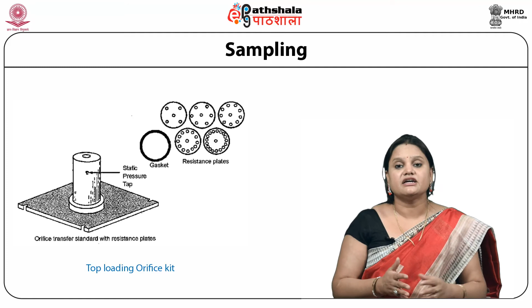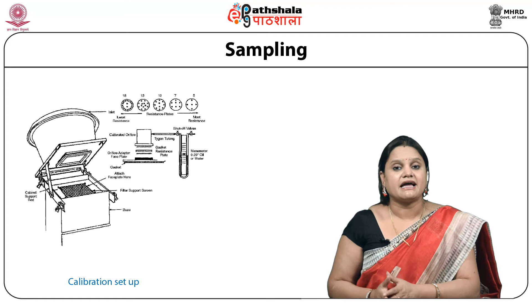Here in the second picture is the top loading orifice kit. This top loading orifice kit is mounted at the upper surface with various types of glass filters having different pore sizes, and here on the side a pressure tap orifice is present, which measures the pressure drop from time to time. Then when we apply these types of resistance plates, the suction capacity of the sampler is identified and the instrument is calibrated from time to time by using such methodology.